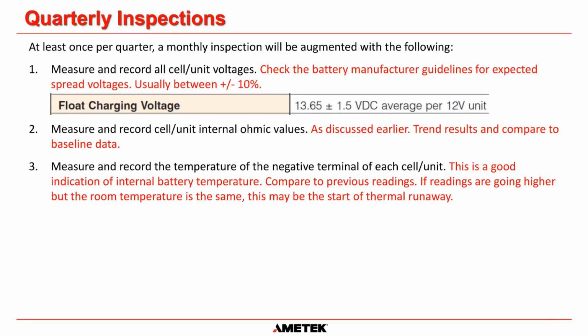What do you do with that reading? Well, if the readings are starting to go high but the room temperature remains the same, that could be an indication that your battery is starting to go into thermal runaway, which is disastrous. If your whole battery goes into thermal runaway, that can cause a fire. So that's why you have to pay attention to these readings and take them correctly, so you can see something that could happen in the future.